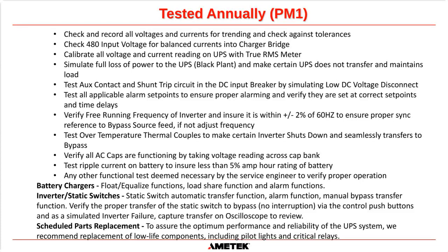We verify that all the AC caps are functioning correctly by taking voltage readings across the capacitor bank. We test the ripple current on the battery to ensure that it's less than 5% of the ampere hour rating of the battery. That's an indication that some batteries are failing. And we do any other functional testing deemed necessary by the service engineer to verify proper operation. So basically, we go through your system with a fine tooth comb.